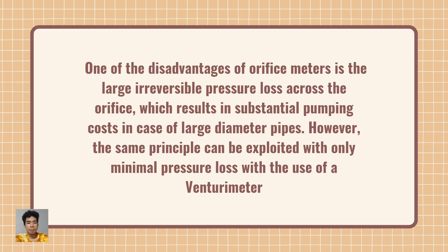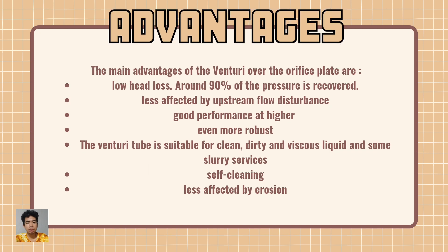However, the same principle can be exploited with only minimal pressure loss with the use of a Venturi meter. The main advantages of the Venturi over the orifice plate are: 1. Low head loss — around 90% of the pressure is recovered.